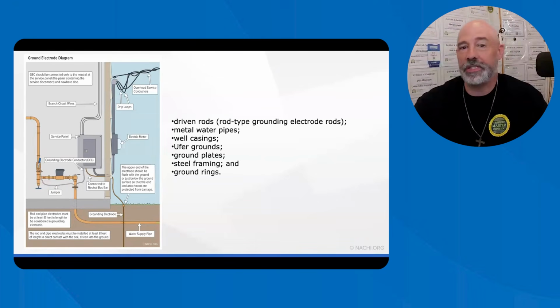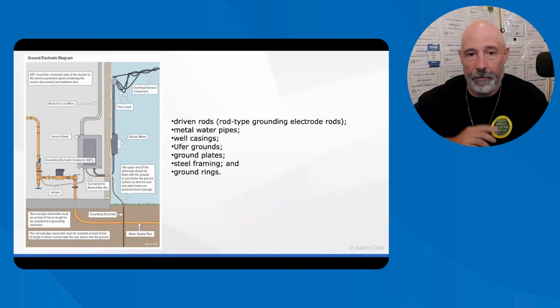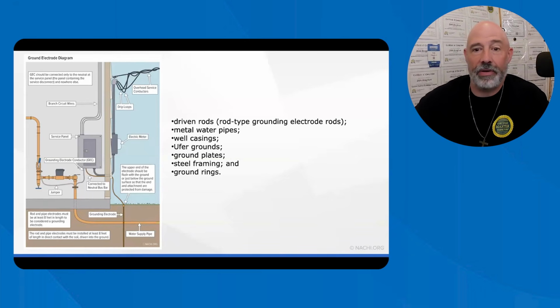Most residential construction requires two separate grounding electrodes in combination of the following, which need to be at least 6 feet apart. You need driven rods. Typically grounded electrodes are the metal water pipes, the well casings, the UFER grounds, the grounding plates, the steel framing, and grounding rings. And a lot of times you're not going to see grounding rings or the grounding plates, just FYI. Historically, the grounding system had just one connection to the ground, and it was nearly always made on the water pipe. Now, however, with most jurisdictions, to ensure a low impedance ground, one with a little resistance.